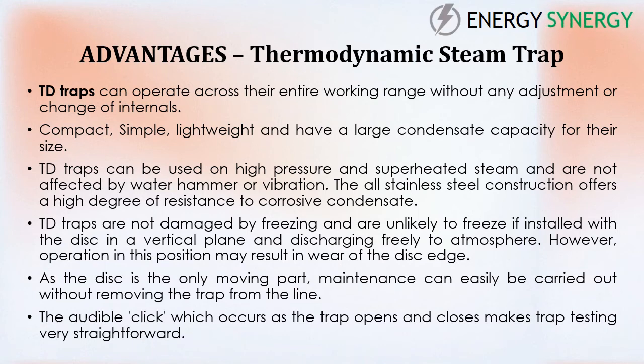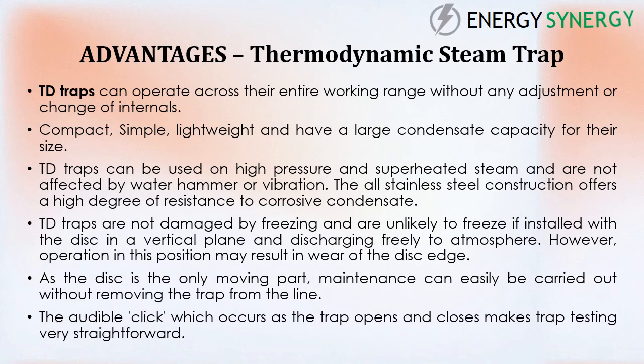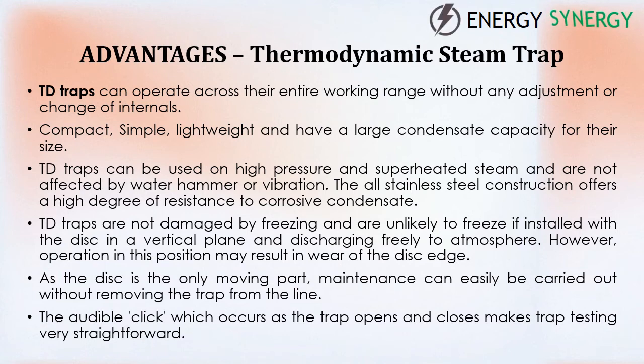(5) As the disc is the only moving part, maintenance can easily be carried out without removing the trap from the line. (6) The audible click which occurs as the trap opens and closes makes trap testing very straightforward.